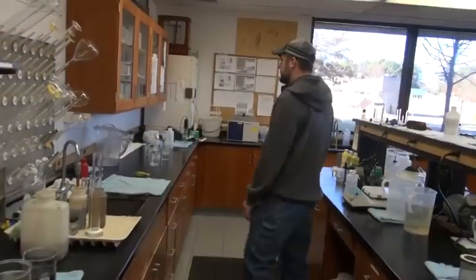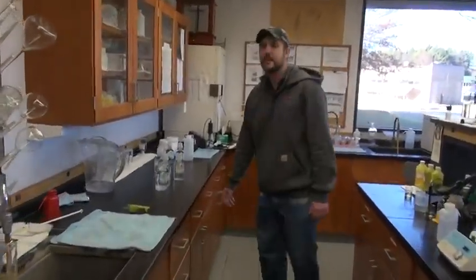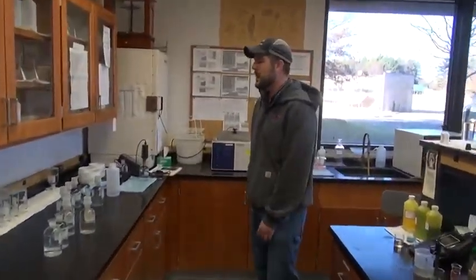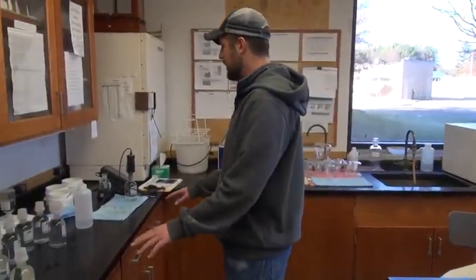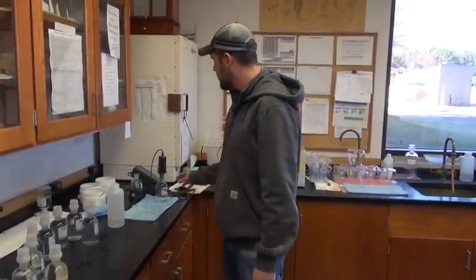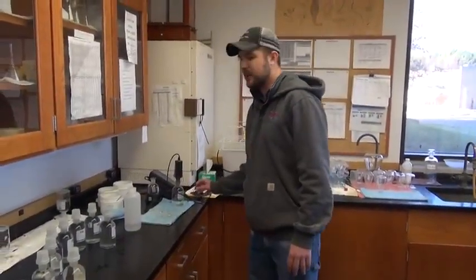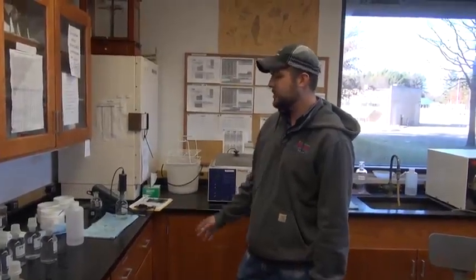Our main test that we do seven days a week is our biochemical oxygen demand test. We monitor that right here. Basically, we are taking a DO probe, measuring dissolved oxygen in versus five days later, dissolved oxygen out. We do some calculations, and we can basically compare the demand of dissolved oxygen to the amount of carbon in your water.